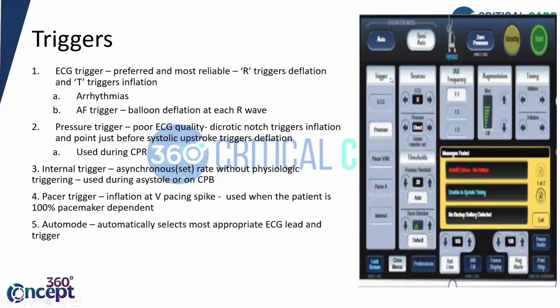The common triggers we see are the ECG trigger and the pressure trigger. Next we have a pacer, ventricular pacer or atrioventricular pacer. So pacer A, atrial pacing. Next we have the internal mode. So let us look at each of the triggers. ECG trigger is the preferred and most reliable. I showed you in the previous picture as well. We'll time it according to the ECG. We will time it according to the T wave and the initiation of the QRS complex. Okay. So ECG trigger is the preferred and the most reliable. R triggers deflation.